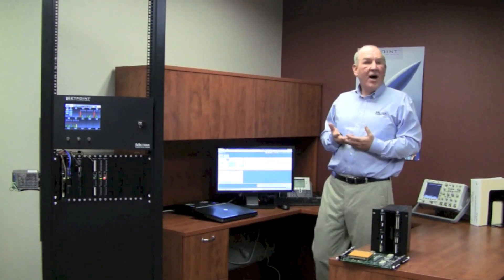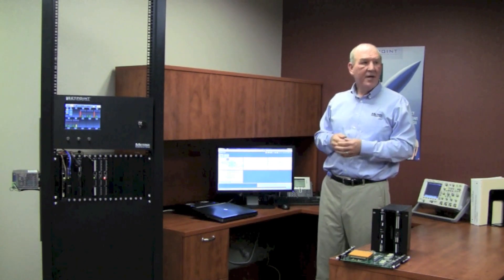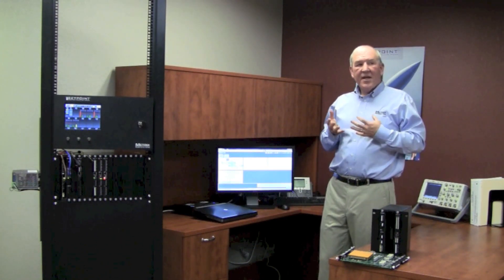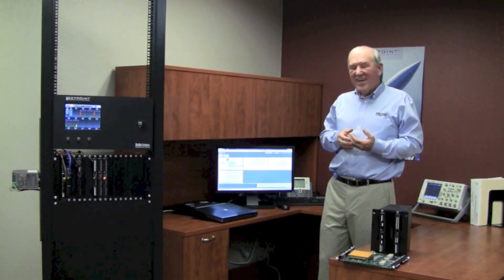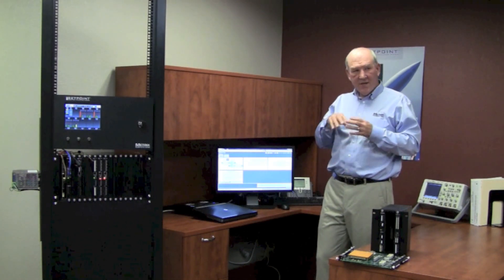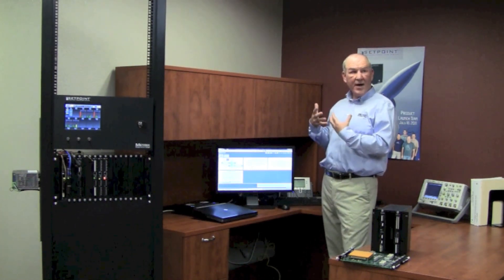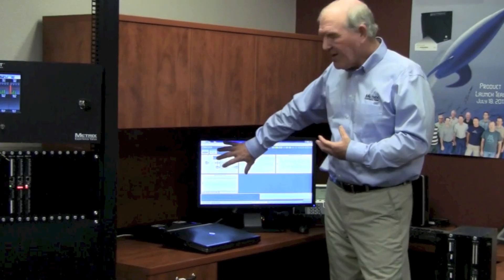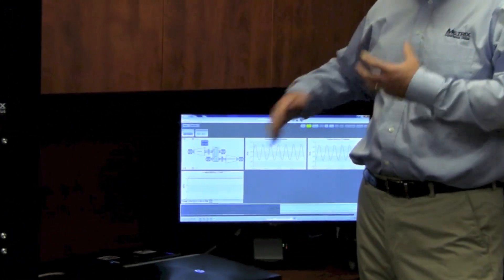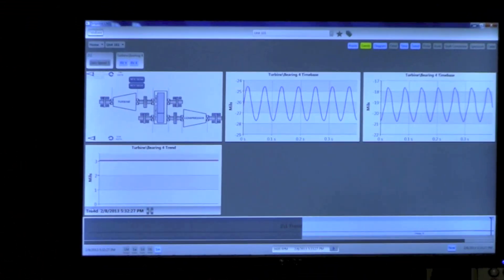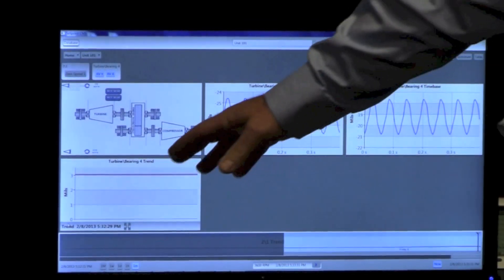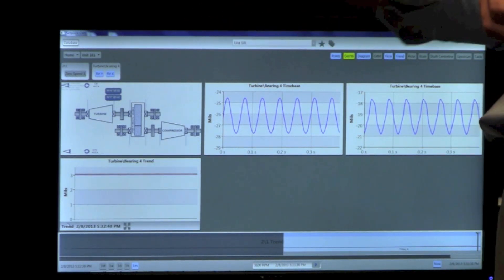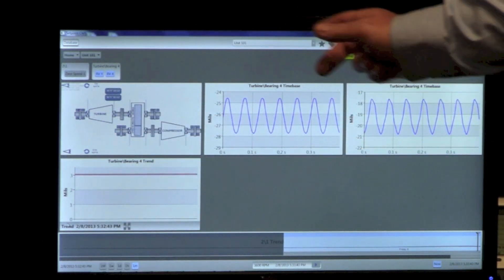There are a couple of ways to view the data. A very common way is to use Pi ProcessBook, which is a very common historian tool used in operations units and plants around the world. Pi ProcessBook is very powerful, but it isn't very good at looking at vibration data. So we're developing here an application that runs on top of Pi — that is our SetPointCMS viewer. This viewer is showing a machine chain diagram with machine statuses, so you can get oriented. We've got a couple of actual waveforms being collected from that rotor kit, and we've actually got a trend. What I'd like to do now is change the conditions of our rotating machinery so we can see the data changing on our condition monitoring software viewer.